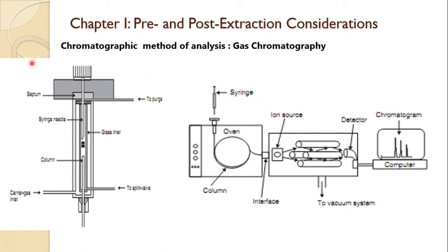Here this is the syringe, and this is the large view of that syringe. Here is the injection port, this is the septum, this end is toward the column, with the carrier gas flow, and a valve for the split and splitless modes. In gas chromatography, two modes are used, one is split and another is splitless. These are two important parameters used for gas chromatography.